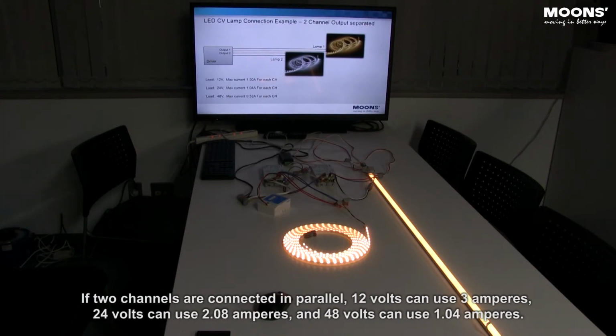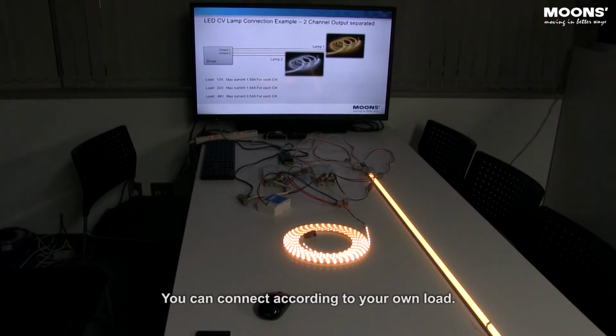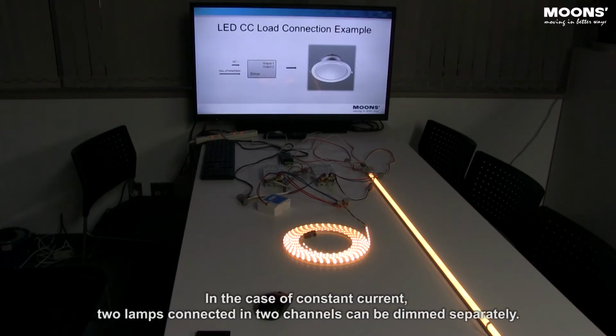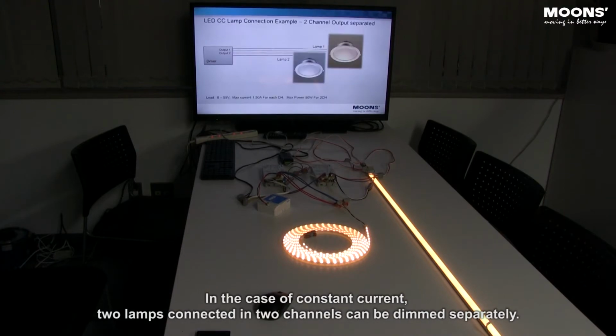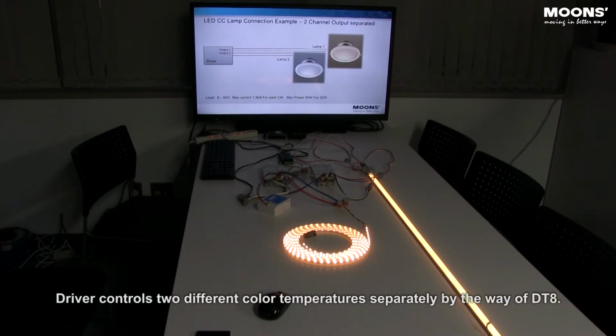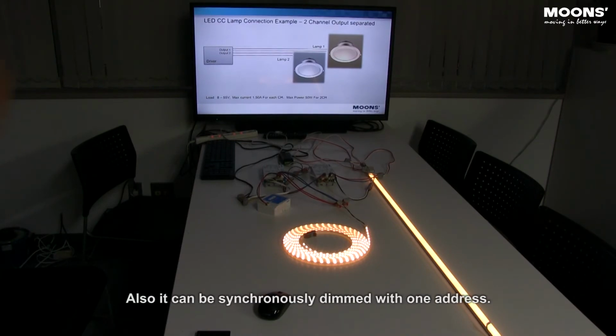If two channels are connected in parallel, 12 volts can use 3 amperes, 24 volts can use 2.08 amperes, and 48 volts can use 1.04 amperes. You can connect according to your own load. In the case of constant current, two lamps connected in two channels can be dimmed separately. The driver controls two different color temperatures separately by the way of DT8. Also it can be synchronously dimmed with one address.